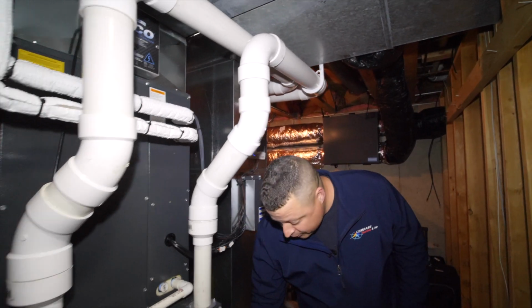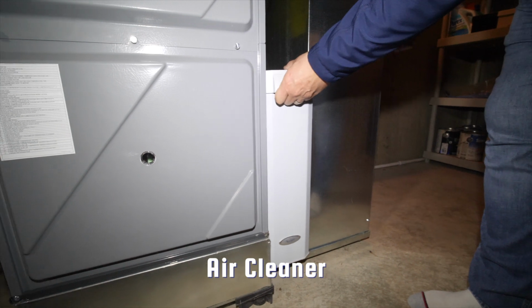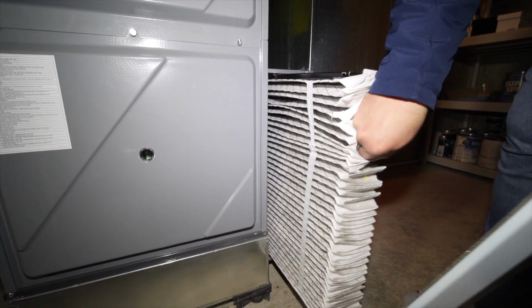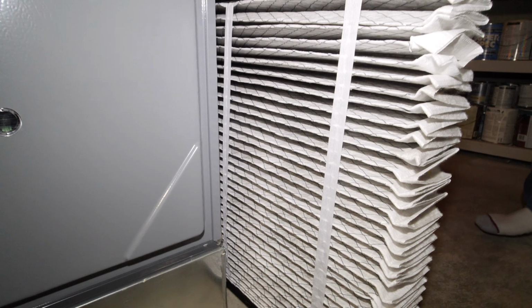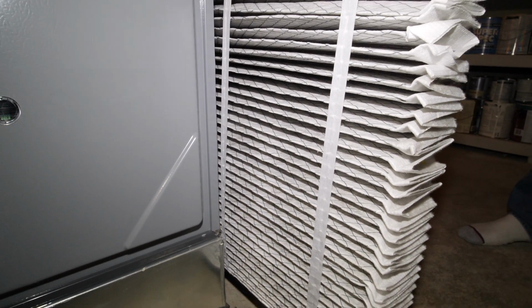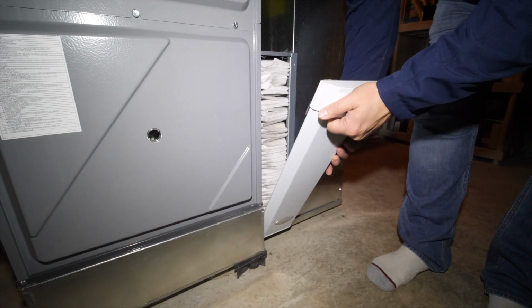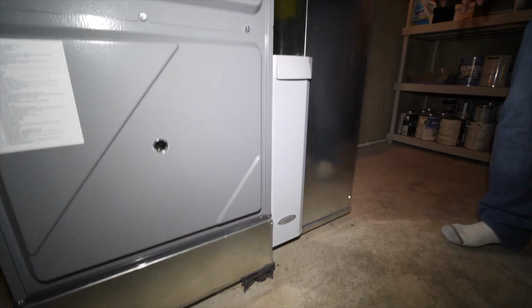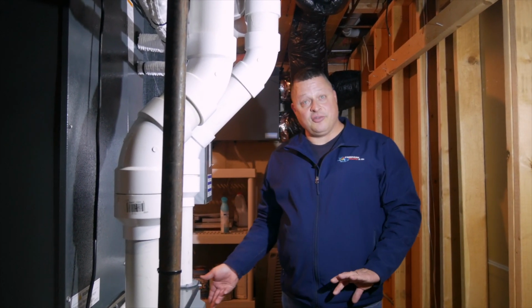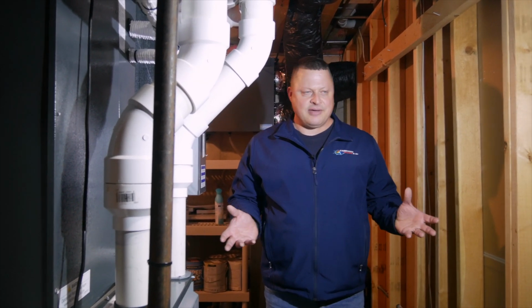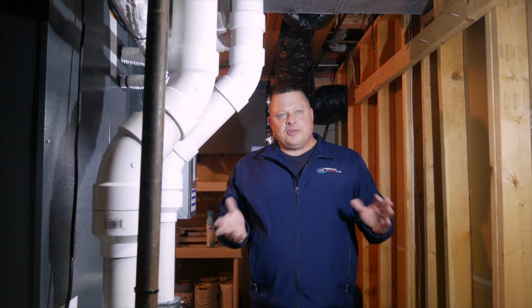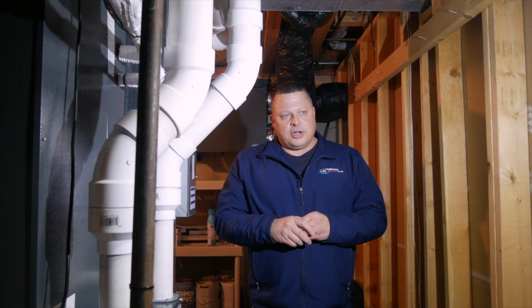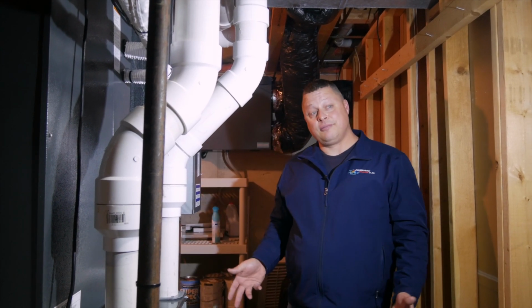Down here we have an Aprilaire air cleaner. This is a 1210, but as you can see, he's already doing quite a job. But we've actually put in a MERV 16. Does really well. Still get really good airflow. Don't really notice any difference in static pressure, which was pretty impressive. When you start hitting the MERV 15, that's when you start being able to trap items such as viruses and bacteria. Anything below that, obviously they do a great job at the MERV 10 and 11 as far as dust and stuff like that, but when you start getting into the smaller things, you need to have a higher MERV, and the system needs to be designed for that.